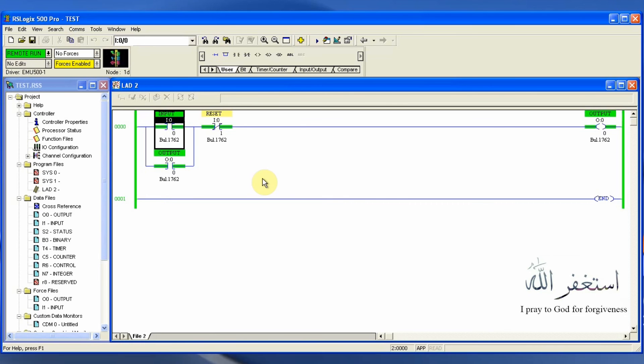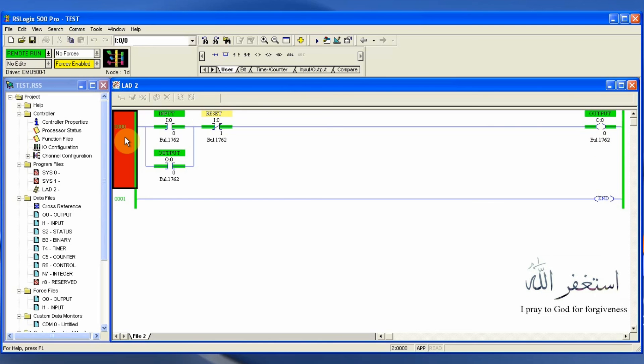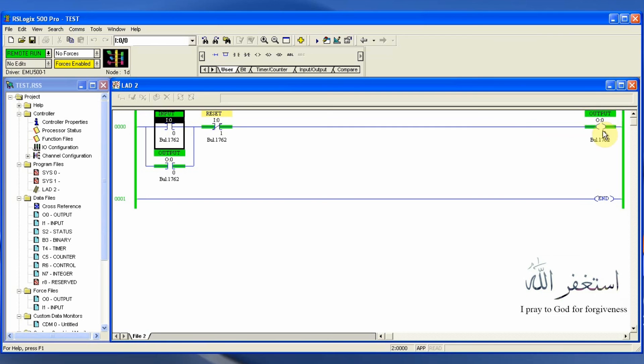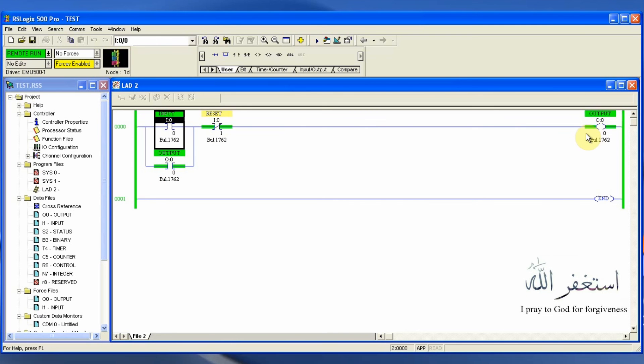If I toggle input I0/0, it turns on this input and our output is also turned on. But now if I turn back this input, the output is still on — because when output O0/0 turns on, its normally open contact O0/0 also turns on, completing the logic path to the output and latching it on.